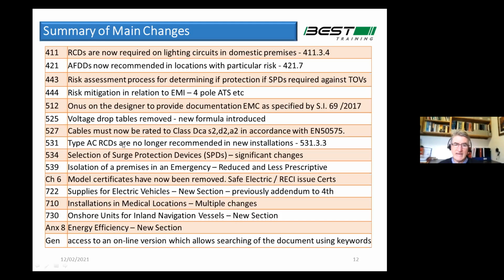Next one is type AC RCDs no longer recommended in new installations. So we'll touch on that later. So basically the recommendation is that we use type A, and in some instances type F or type B, which are a very expensive alternative compared to a type A RCD. Surge protection devices, lots of new information in that section on how to select them, how to be configured inside the panel and everything inside the distribution board. So lots of information on that.